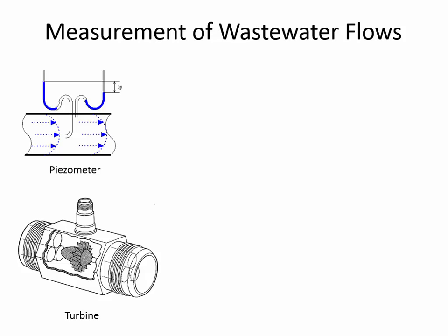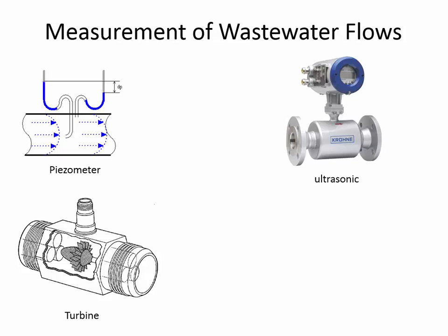A turbine flow meter overcomes some of those limitations. As shown in this depiction, there's a propeller inside the pipe that spins faster with increasing flow rate. Before it's put into service, a curve is made relating the rotational rate of the turbine to the average velocity inside the pipe. The manufacturer gives you a chart saying how quickly it's spinning versus the flow rate. The advantage is you can measure remotely, record data over time — it's much more sophisticated than a piezometer.